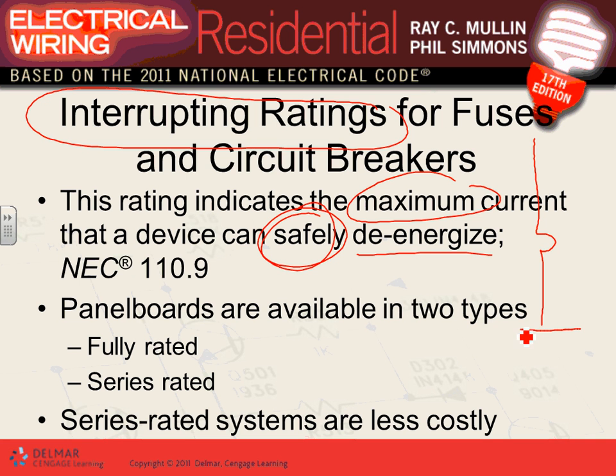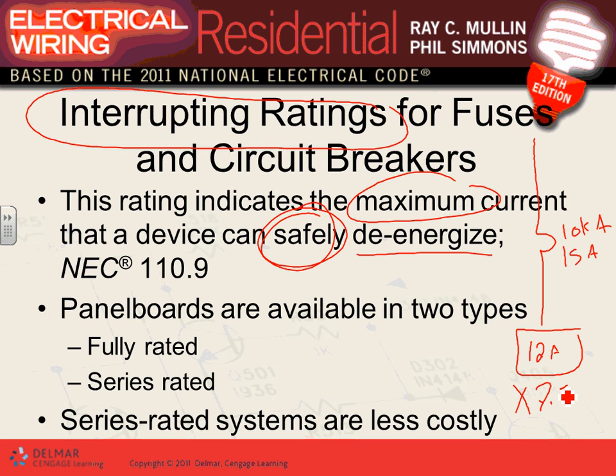For example: a 15-amp circuit breaker with a 10,000-amp interrupting rating, feeding a 12-amp load, with a short circuit condition of 7,500 amps. Under normal operating condition the load is fine. For the short circuit — 7.5 kA — and the interrupting rating is 10 kA: as long as the short circuit is less than or equal to the interrupting rating of the circuit breaker, you're safe.